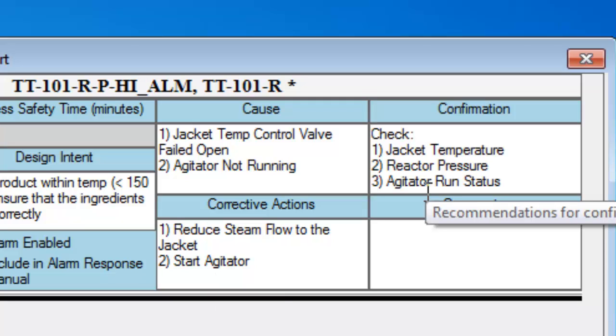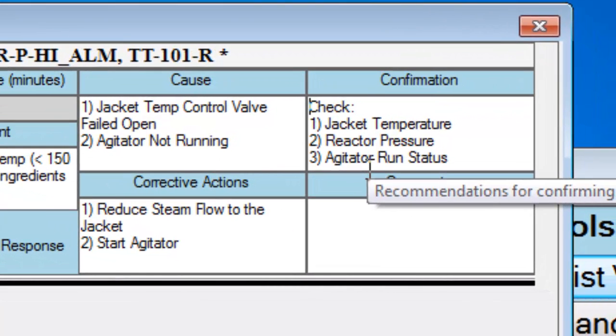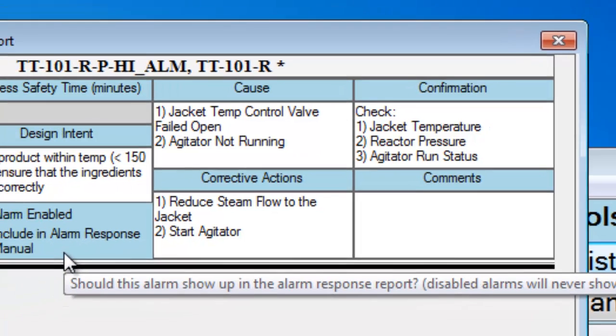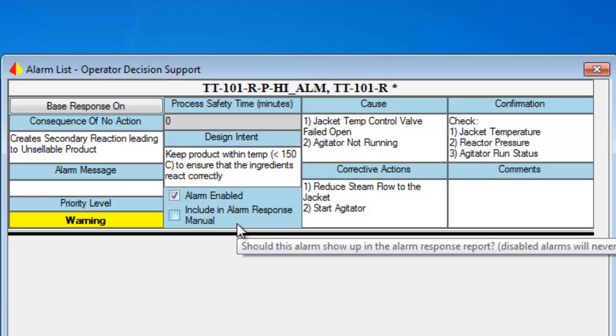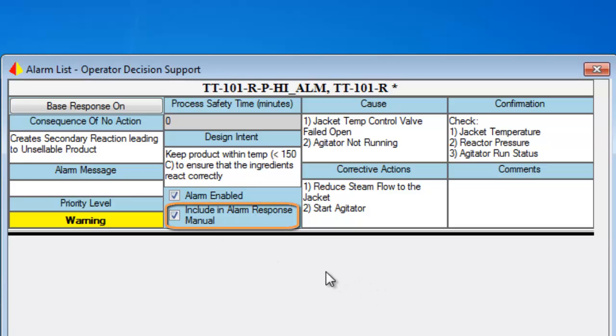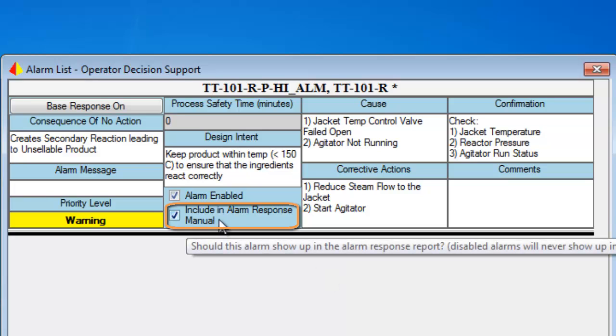If you've ever heard the expression "the cure is sometimes worse than the disease," you'll understand why it's important to document how to confirm that the alarm is real. No one wants to shut down production, but if that's what's required to protect the safety of the plant and its people, then the operator should be empowered to do so. Documenting other process measurements or conditions that the operator can use as confirmation will help them take the necessary action and determine which cause initiated the alarm. Alarm rationalization can be thought of as a knowledge capture process, since key participants include experienced senior operators. A side benefit is that the information captured can be made available to all operators, including junior operators, to help them respond to alarms more effectively and consistently. This operator alarm response aid is called an alarm response manual, alarm response procedure, or alarm help in some control systems.